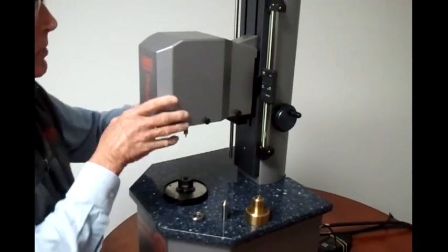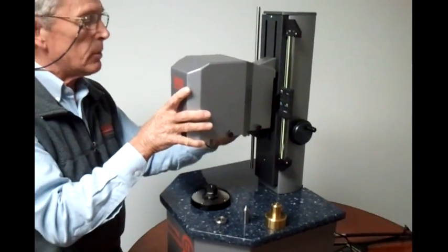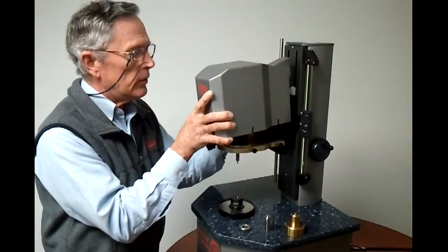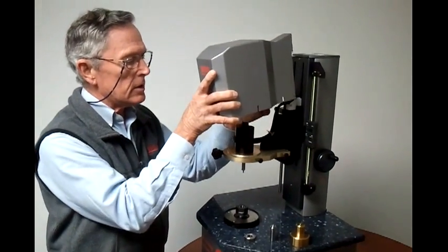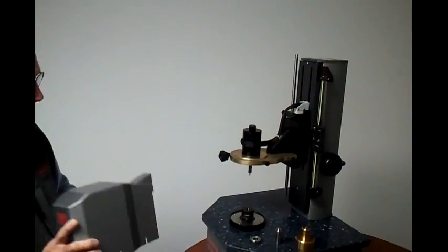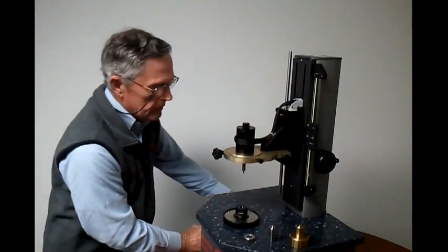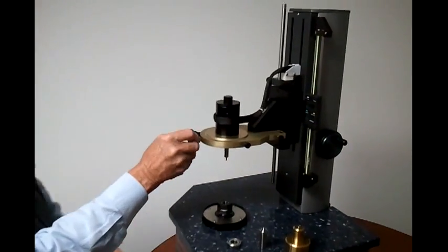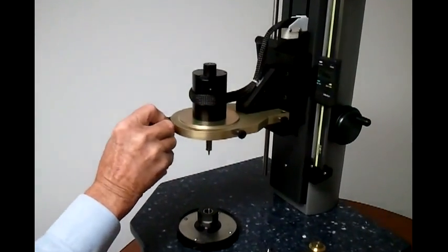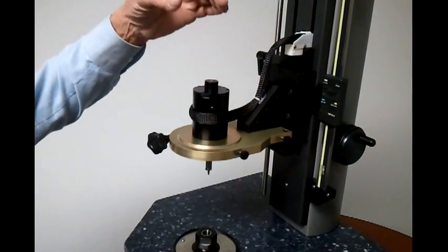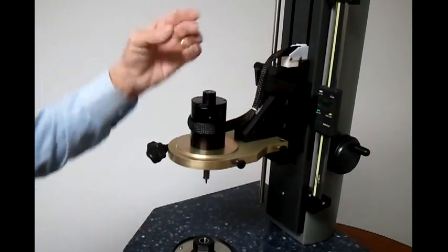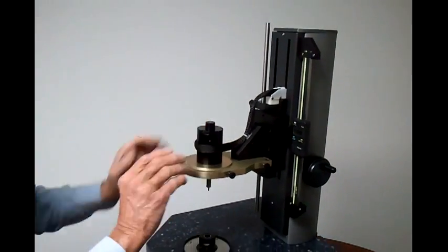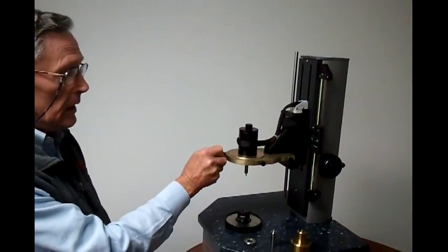Many different transducers can be supplied to work with this system for different torque ranges. To change the transducer the cover lifts off, this device is loosened and the transducer just lifts out. We unplug it and you can put another transducer in and tighten it up.